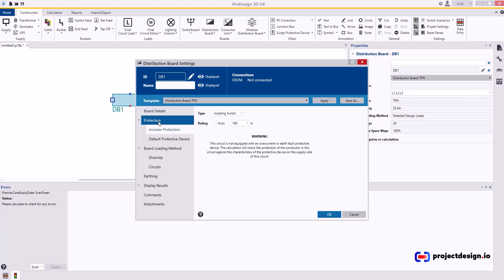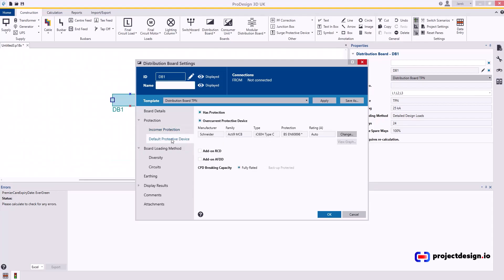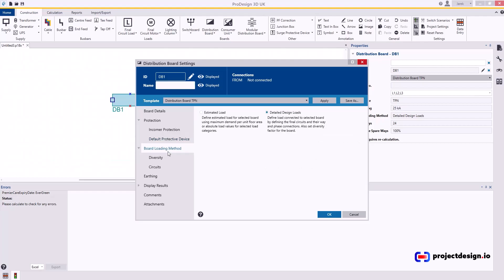Protection—typically the distribution boards will have an isolating switch, not a protective device, and then rated 160 amp. Default protective device is inherited from my template, which in this case is Schneider Acti 9 MCB, and the rating is auto at the moment, but I will be changing it to a specific rating.